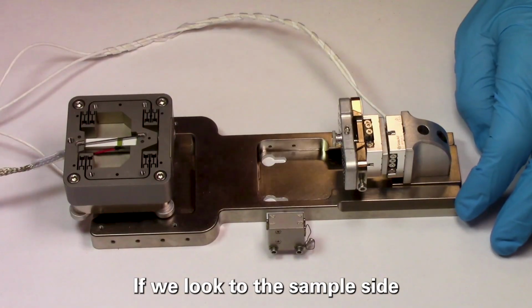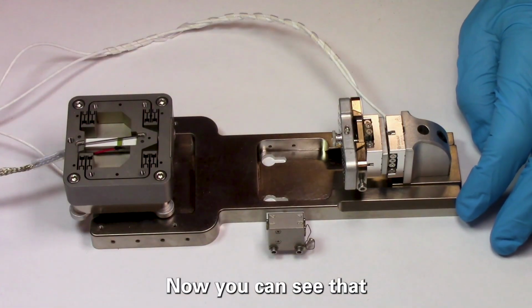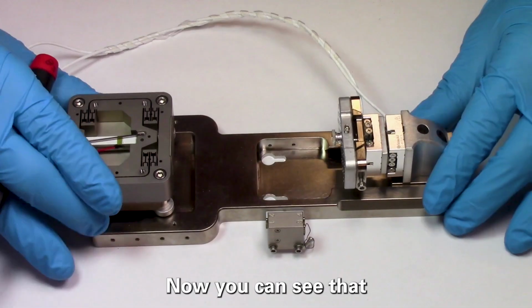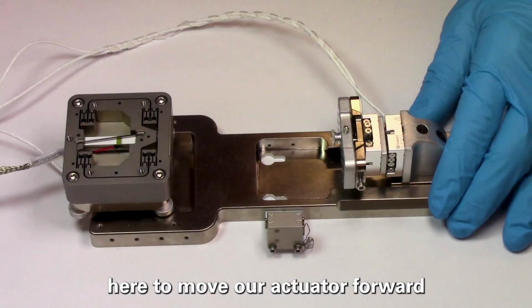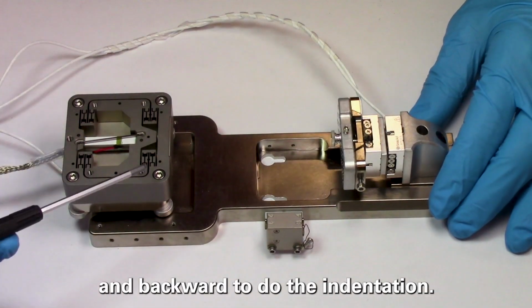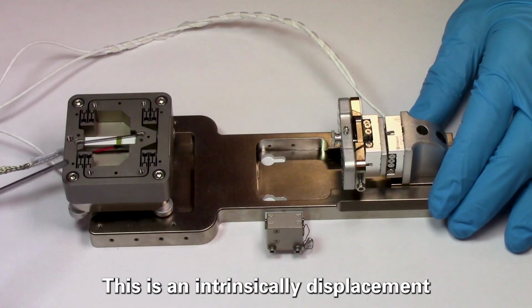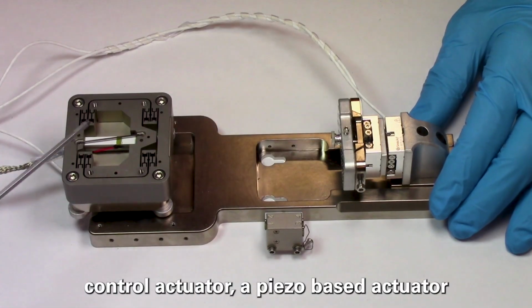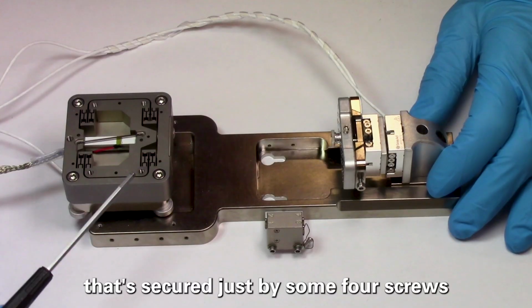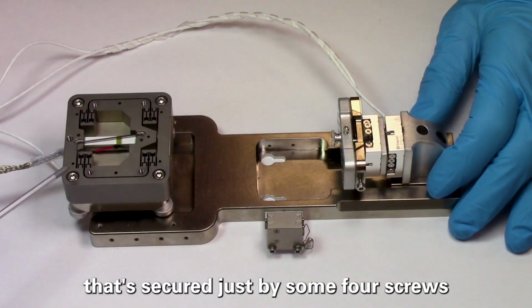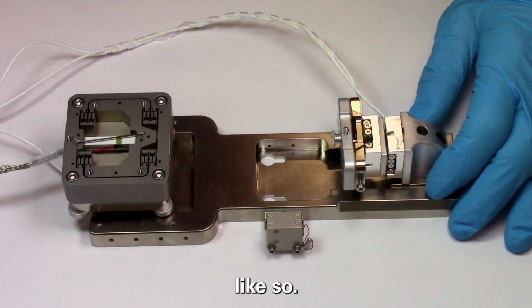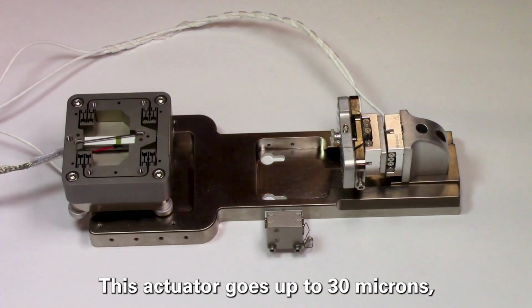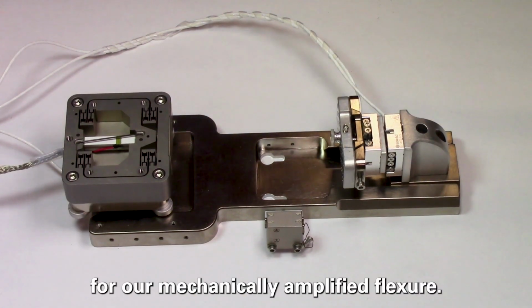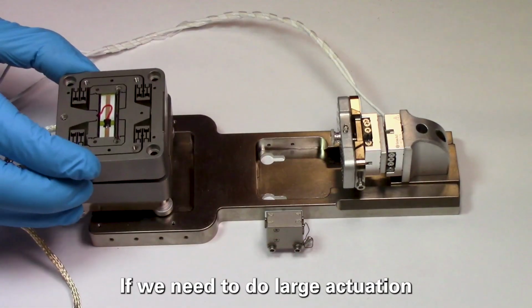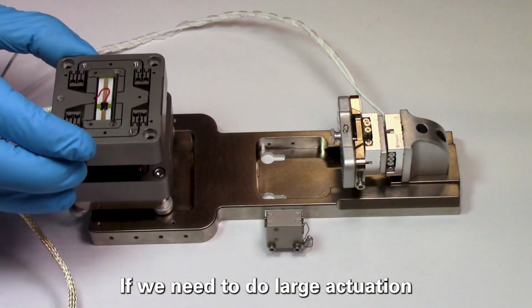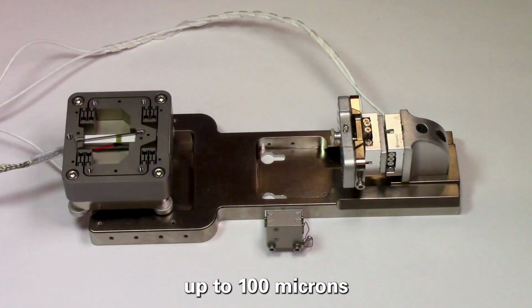If we look to the sample side, or the actuation side now, you can see that there's another set of stages here to move our actuator forward and backward to do the indentation. This is an intrinsically displacement controlled actuator, a piezo-based actuator. It's secured just by some 4 screws, like so. This actuator goes up to 30 microns, but we can also swap out for our mechanically amplified flexure if we need to do large actuations to 100 microns.